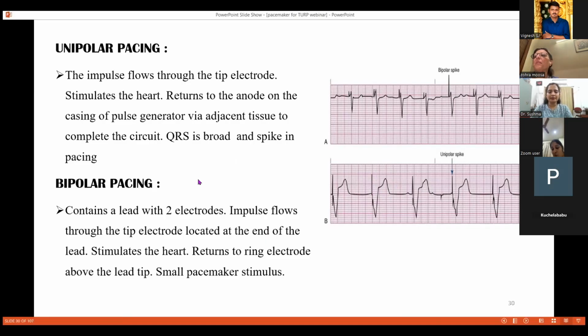In bipolar pacing, here there are 2 electrodes. Impulse flows through the tip electrode located at the end of the lead. It stimulates the heart and this returns to the ring electrode above the lead tip. Here the pacing spikes are small.